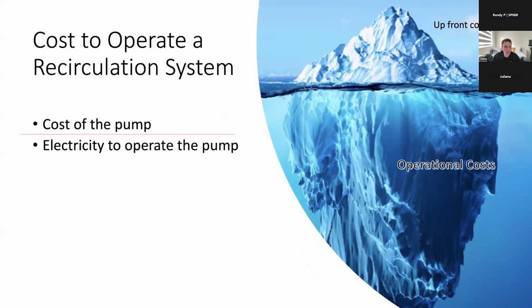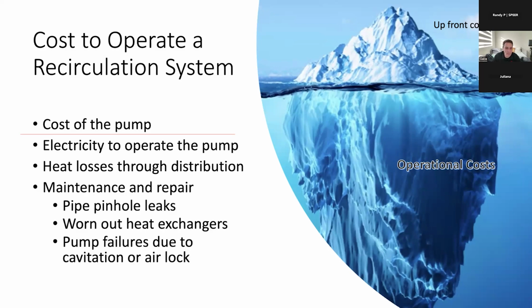So if you look below the line, you have number one, the electricity to operate the pump. That's one cost. You have heat losses through your distribution pipes, and I'll get to more on that in a second. And then you have wear and tear, maintenance and repair from circulation flows that can create pinhole leaks, worn out heat exchangers for your tankless water heaters, et cetera, et cetera. Now, here's the big question for you all. If you were to guess what the biggest cost is of these three things, what do you venture would be?